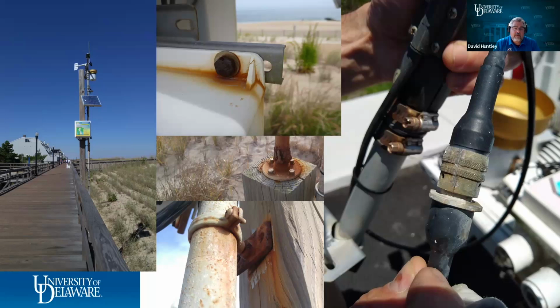That bolt was common steel. It should have been stainless steel to match the bracket behind it. When you put stainless steel and common steel together, the common steel oxidizes faster and swells. As it swelled up, you can see where it broke the enclosure. There's that crack, starting here and running down below the bolt. That crack is because of the common steel corroding.